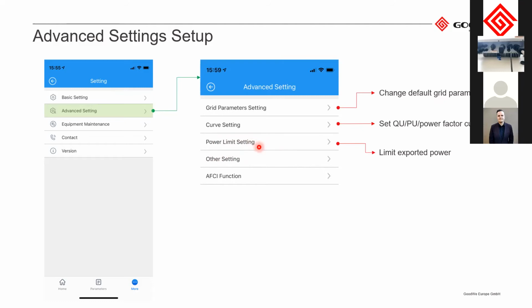And in case you do have the smart meter connected, as we have done in this case, then the CTs will measure so that the inverter can produce max power for the loads, but it will not produce more than the loads can take, and therefore not export any power into the grid. If you do not have a smart meter installed, it will just limit the power output of the inverter. So it will just be like a limiting factor. Here you can change the power factor of the inverter, for example, and in case you have an inverter with AFCI function, then you can turn it on or off in this menu here.